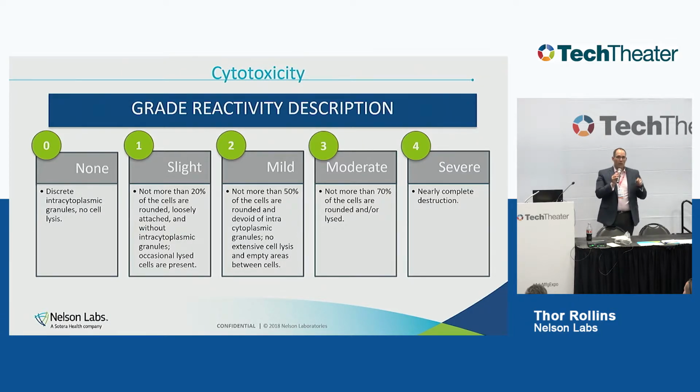I will also tell you, if you're submitting to the FDA, if you have a 2, you probably want to have some evaluation of that 2. Because even though it's passing, the FDA is like, whoa, that's close. We want to know what's happening. If you score 1, you're fine. Don't freak out about a 1, okay? In fact, don't really freak out about any score, because most of the time when you fail cytotox, it's not a clinically relevant failure. But if you have a 1, it goes through the regulatory bodies really easily, okay? So this is, like I said, done in vitro right now. It's something that we currently run 60 to 80 of them a day, right? So it's a very routine test we run every single day.